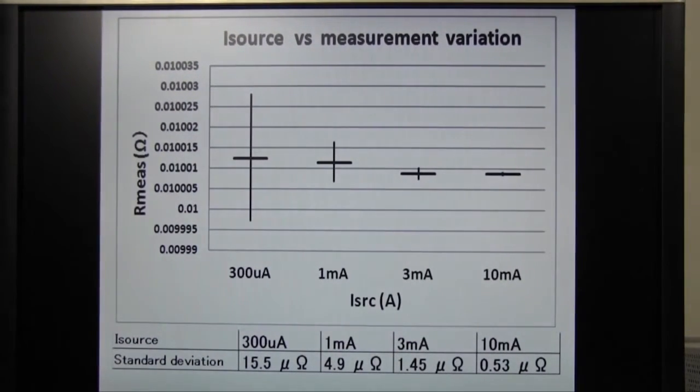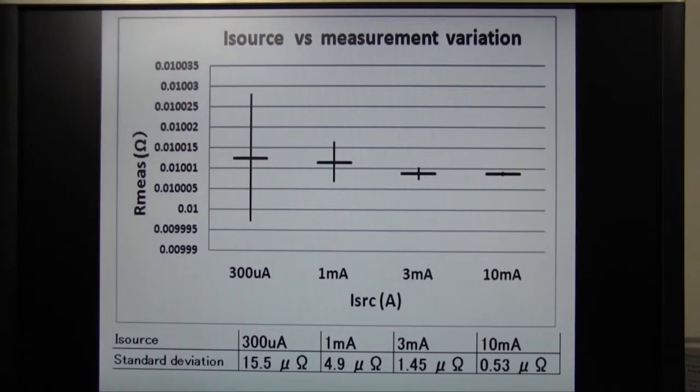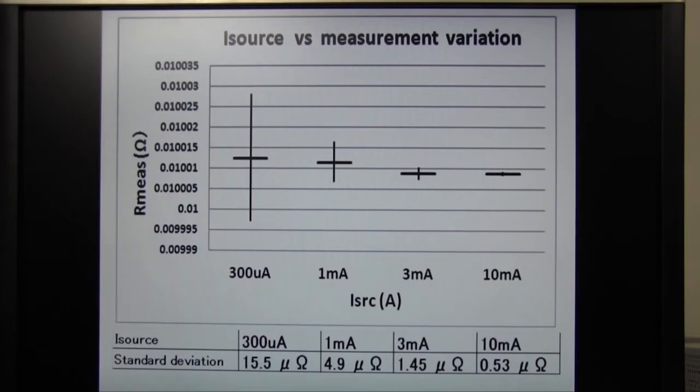This is a measurement result of 4 different force currents. The vertical bar shows the standard deviation. It shows that the standard deviation gets smaller when forcing a large current. You can set the best force current regarding the noise and the damage of the device.